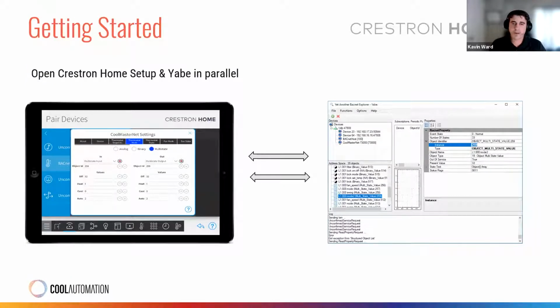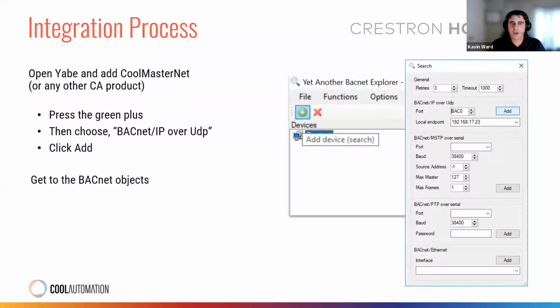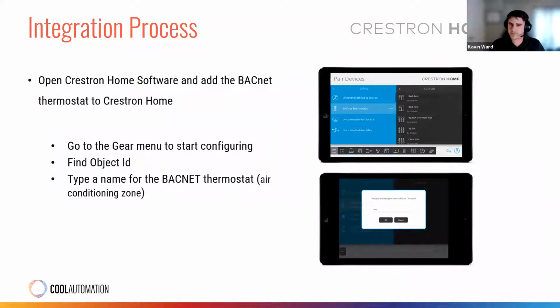So you're going to have Yabe open as well as your Crestron Home Setup tool. You're going to first discover the device on Yabe. And by doing that, once it's open, there's that green plus icon in the top left. You'll choose BACnet IP over UDP. Make sure your local endpoint is correct, and then click add. From there, your devices will populate. You'll likely see the Crestron controller as well as the CoolAutomation device. By default, our address is going to be 64.